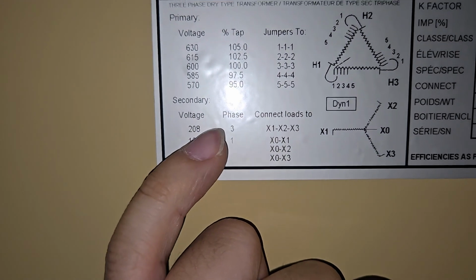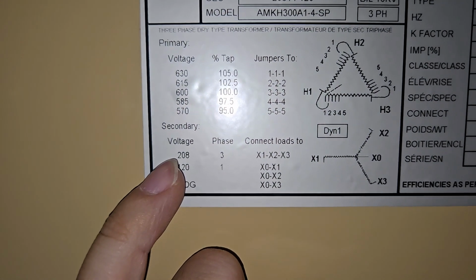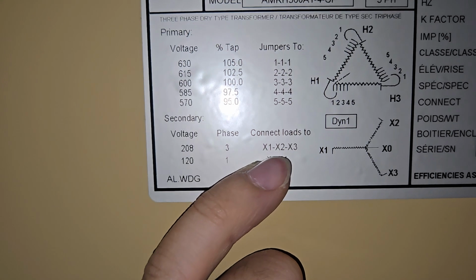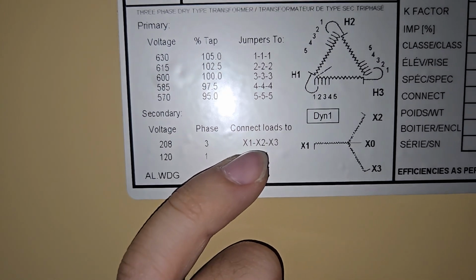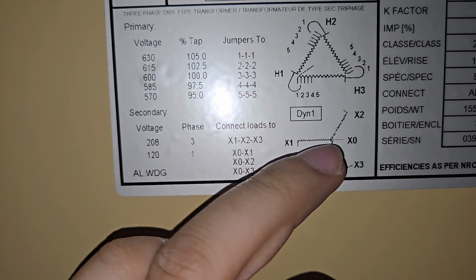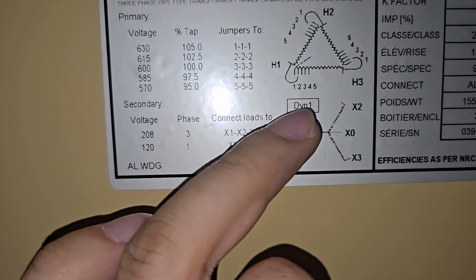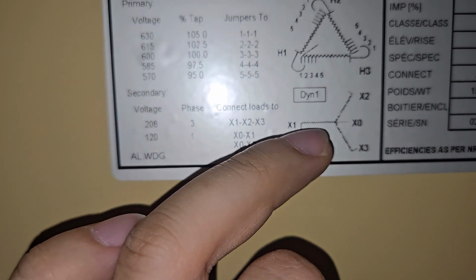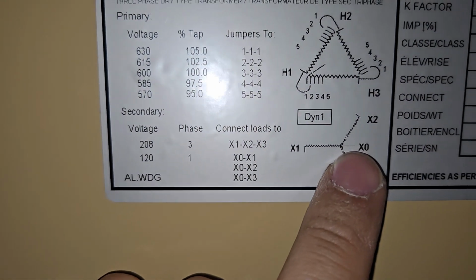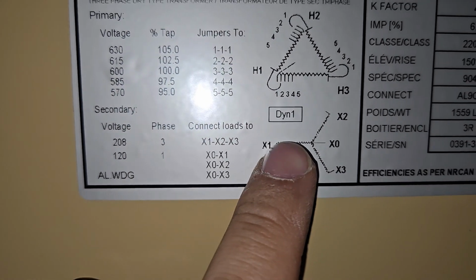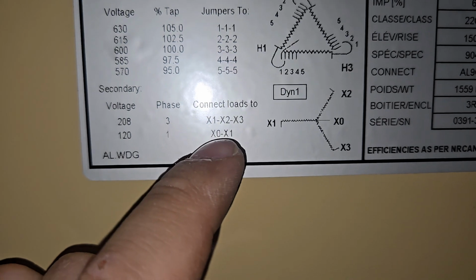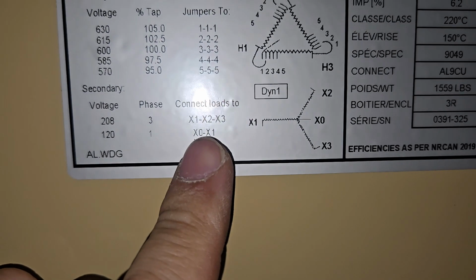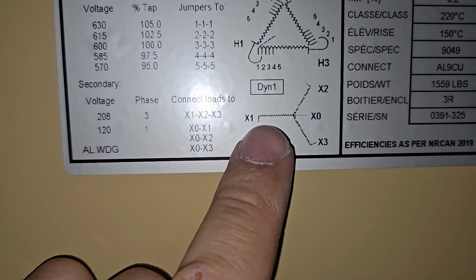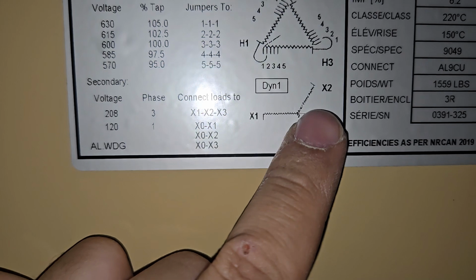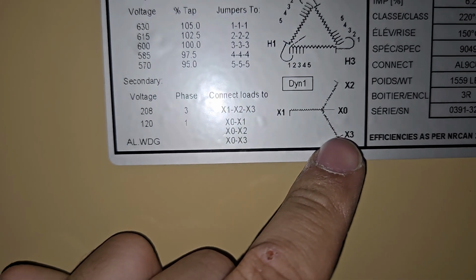But basically, if you set this up as a 3-phase system, then you get 208 volts across the three. So when you look here, the way these are wired, you got 3 phases that are out at different angles, because this is alternating current. And they're 120 degrees apart, so this is actually like a sine wave. And in the center you've got your neutral, which is x0, and your phases are x1, x2, and x3. So you can connect a single phase panel, for example, to x0 and x1, or x0 and x2, or x0 and x3, and you can get power that way from your neutral.